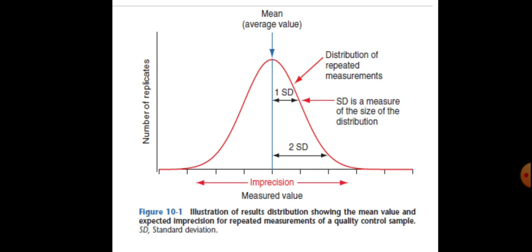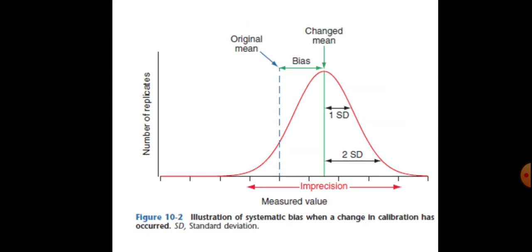This is about the graphs showing the measured value, that is, an illustration of results distribution showing the mean value and expected imprecision for repeated measurements of a quality control sample, where the standard deviation is taken into account. On the x-axis imprecision is taken, on the y-axis the number of replicates, and the mean value is shown with one or two standard deviations. This graph illustrates systematic bias when a change in calibration has occurred. The shift of the graph is seen to the right side, while the x-axis and y-axis are the same: imprecision and number of replicates.